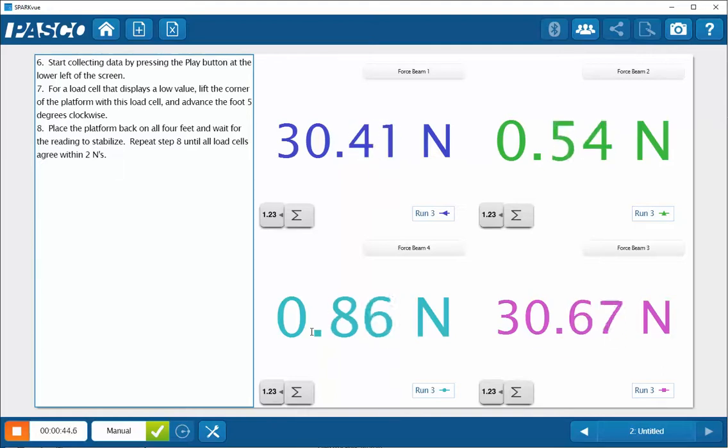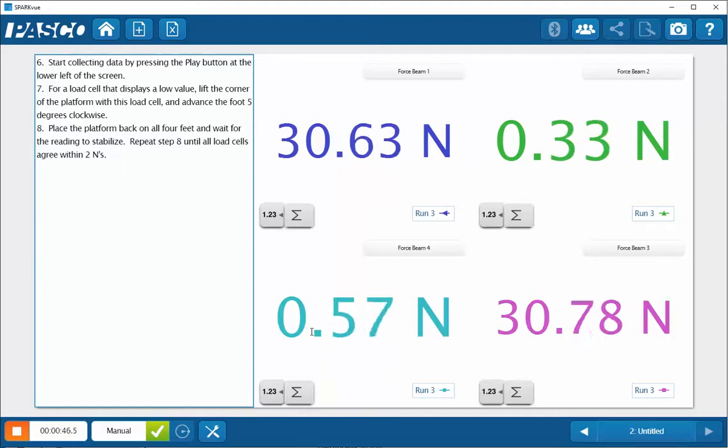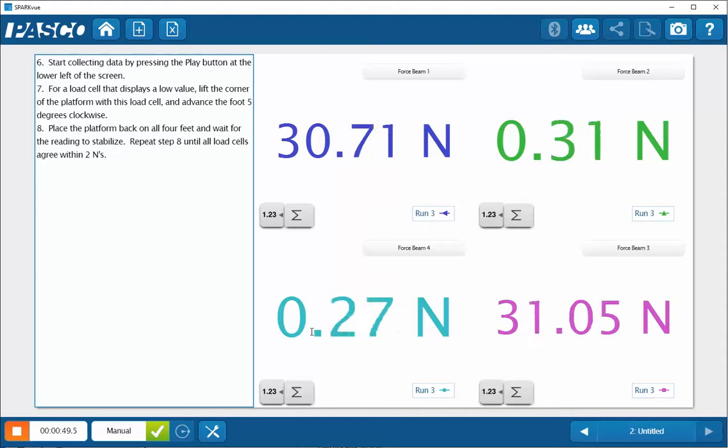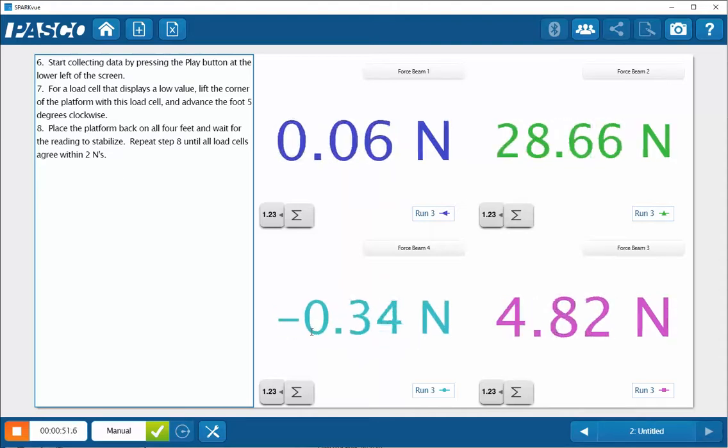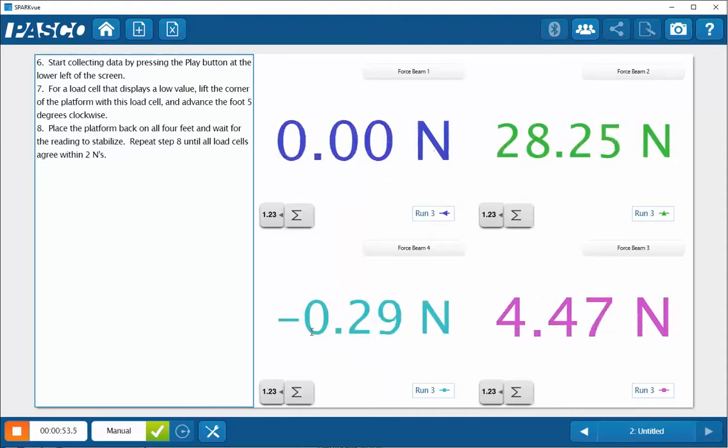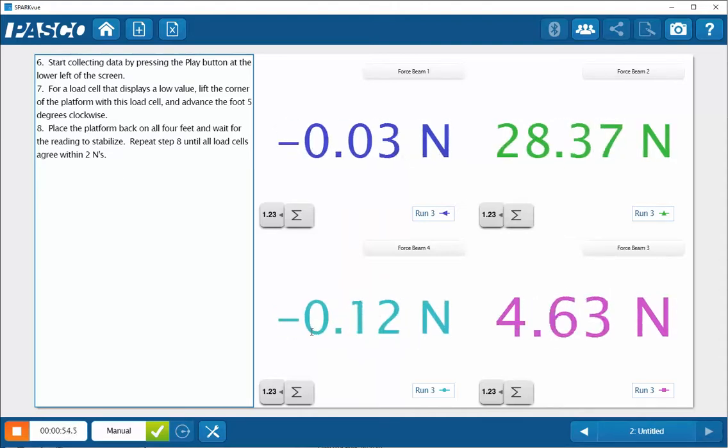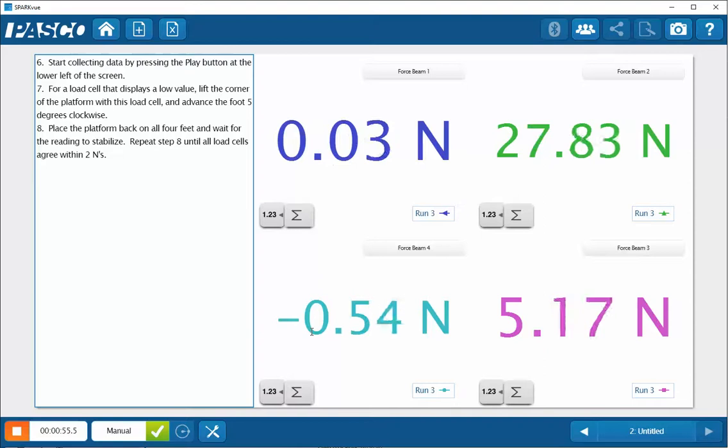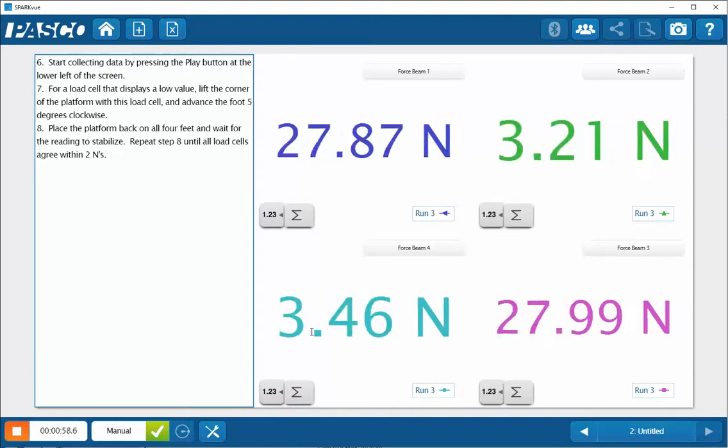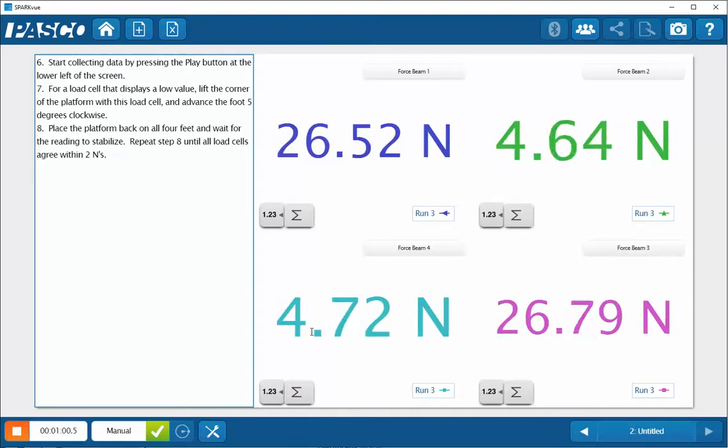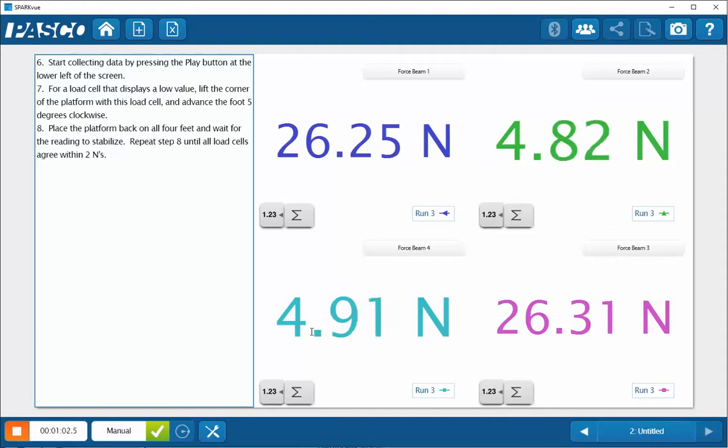So I'll do that by raising the corner of the platform that has the foot that I want to advance, lift it gently, and then turn the foot about five degrees clockwise. That will advance the foot and you can see that that has started to provide some load on that foot.